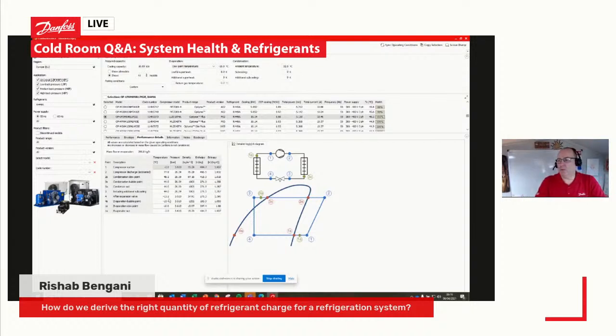And basically what Cool Selector does is it gives you the p-h diagram, which is all well and good, but then it also gives you a nice pictorial system picture of your refrigeration system. And then on the left-hand side here, it gives us a description of the points. So we've got compressor suction as point 1, compressor discharge as point 2, and it will tell you your temperature and pressure that you would expect on that system given the evaporating temperature and the ambient temperature.